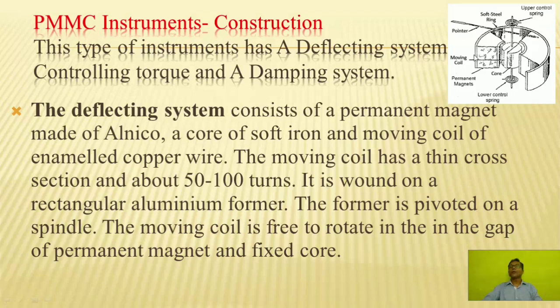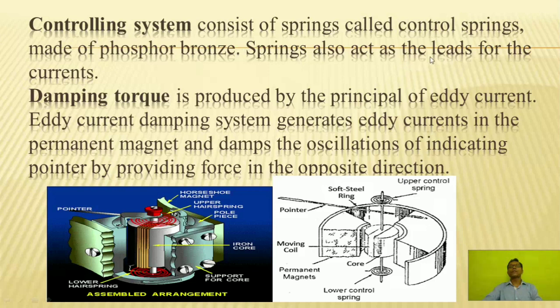This deflecting system consists of a permanent magnet made of alnico, a core of soft iron, and a moving coil of enameled copper wire wound on a rectangular aluminum former, pivoted on a spindle. The controlling system consists of control springs made of phosphor bronze, which also act as leads for the currents. Damping torque is produced by the principle of eddy current. The eddy current damping system generates eddy currents in the aluminum former and damps oscillations of the indicating pointer by providing force in the opposite direction.